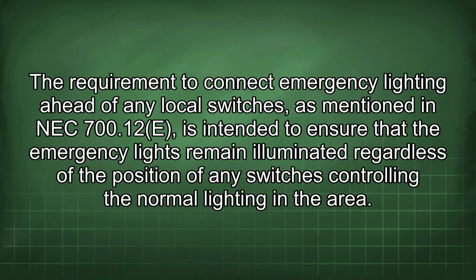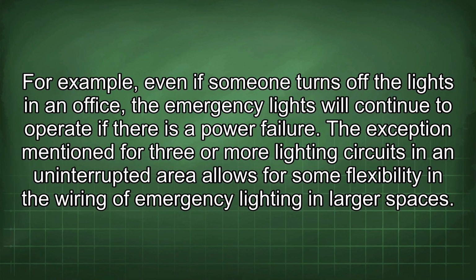The requirement to connect emergency lighting ahead of any local switches, as mentioned in NEC 700.12(E), is intended to ensure that the emergency lights remain illuminated regardless of the position of any switches controlling the normal lighting in the area. For example, even if someone turns off the lights in an office, the emergency lights will continue to operate if there is a power failure.